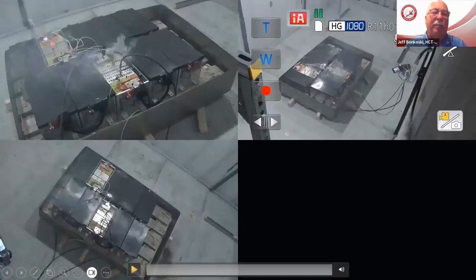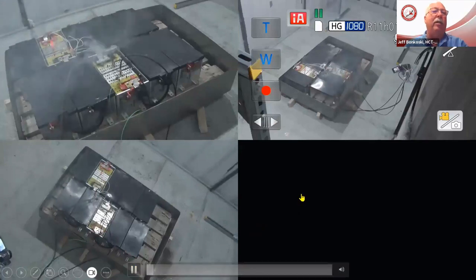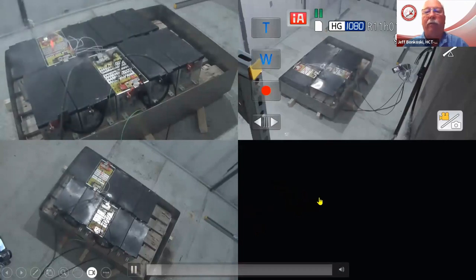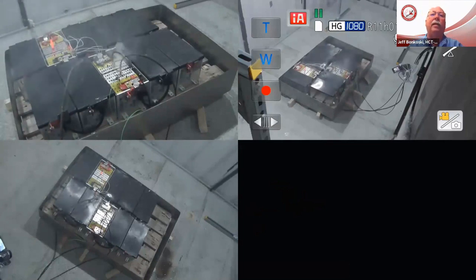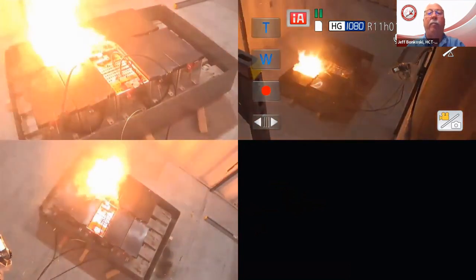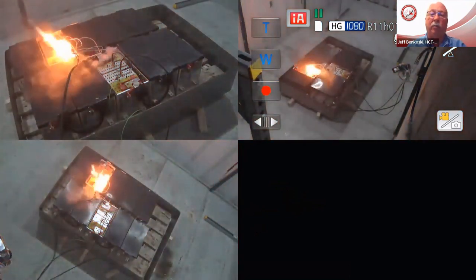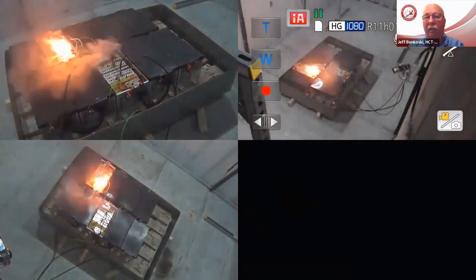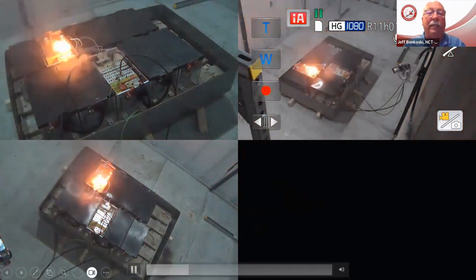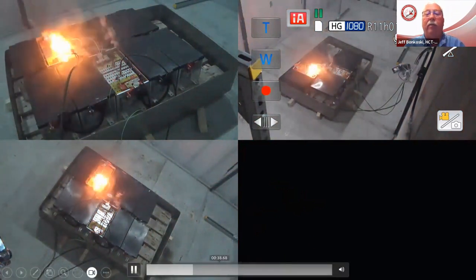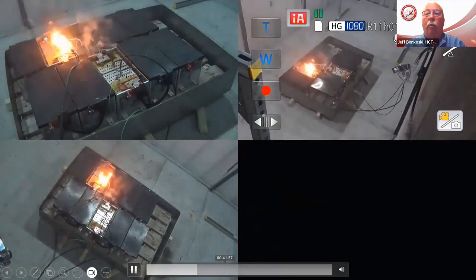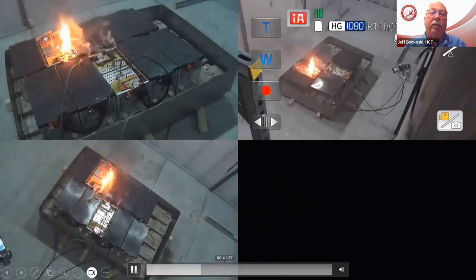This test was done by TU Clausthal. This is a large battery found in a utility vehicle, put into a Connex box with two pendant style sprinkler heads. They let the battery go into thermal runaway and thermal propagation, letting it burn, to see how effective a fire sprinkler system would be at extinguishing a lithium-ion battery fire.